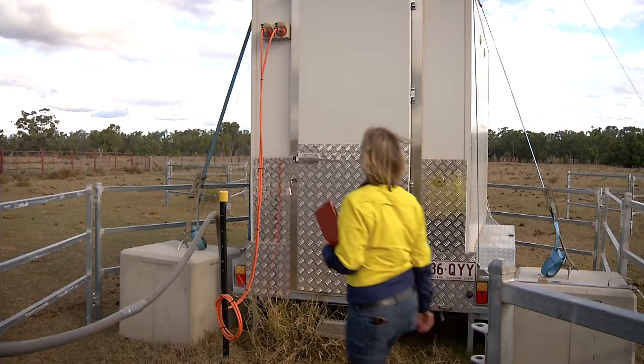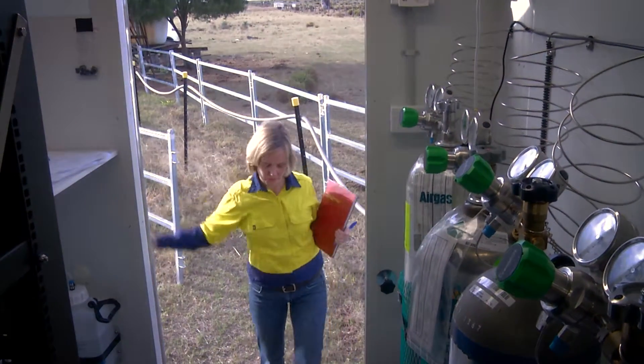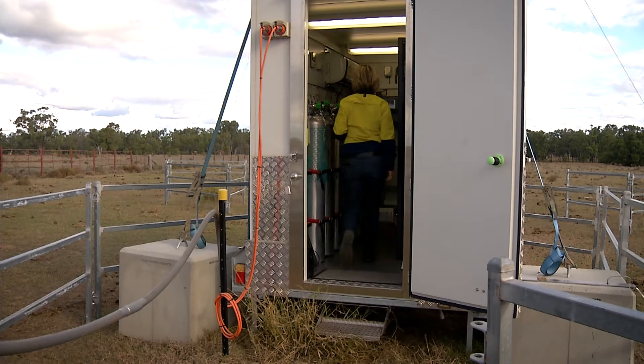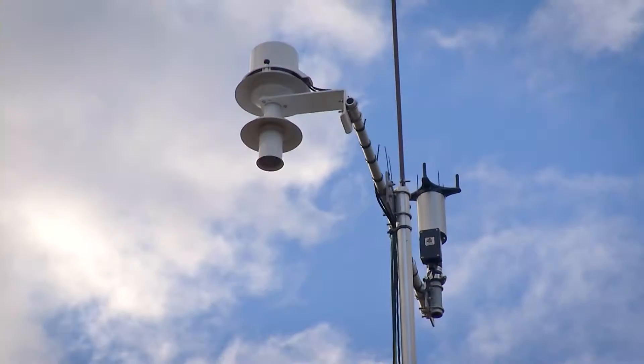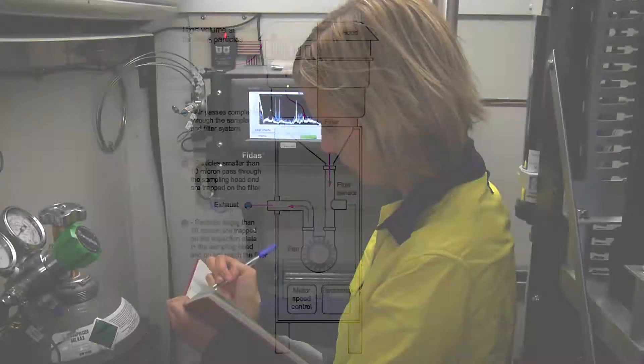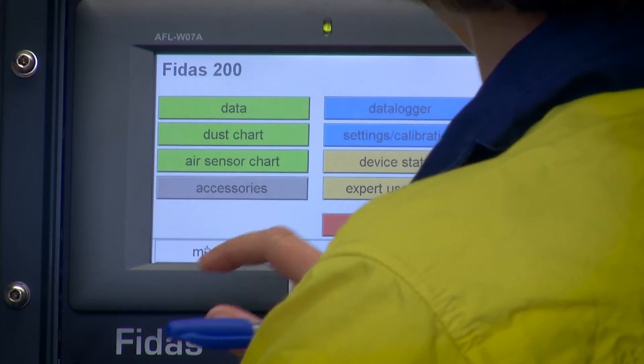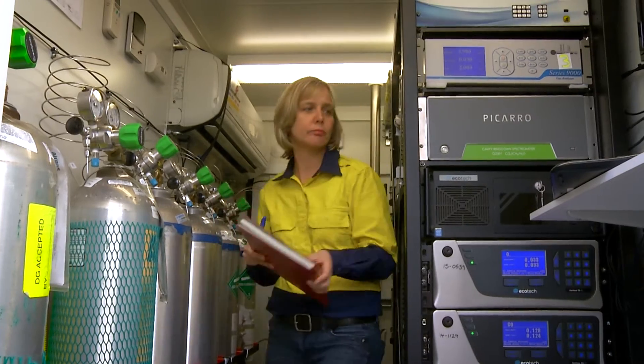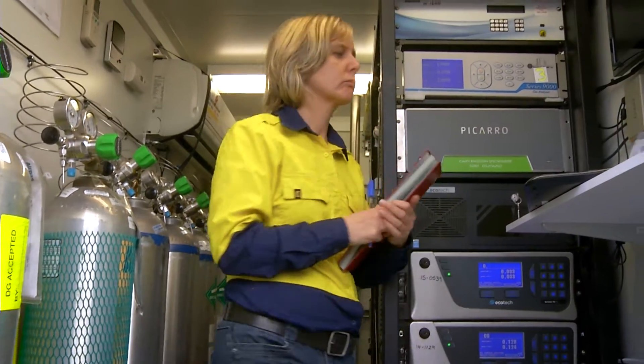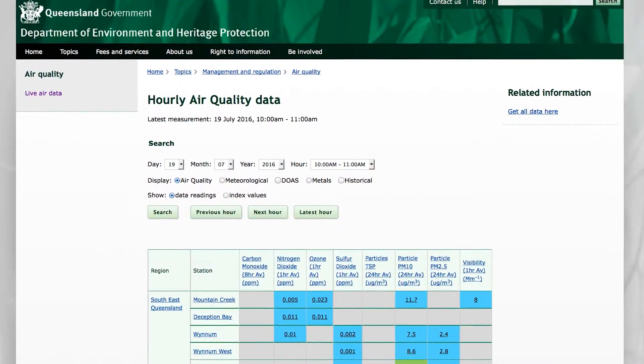An ambient air quality station is really a building which contains a whole lot of really specialised ambient air monitoring equipment. We have an inlet and the air is drawn down the inlet via a pump, and then each of the specialised instruments takes a little bit of that air, analyses it for the selected pollutant, and then provides the reading or the pollutant concentrations to the computer where it's then streamed to the EPA website.